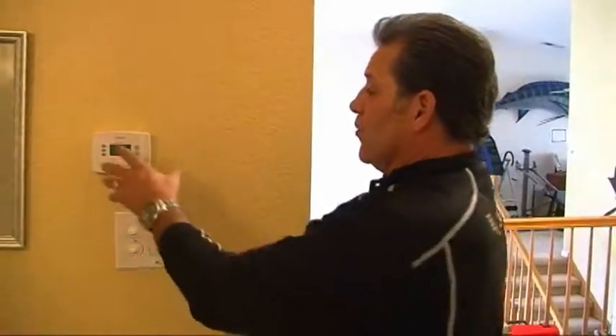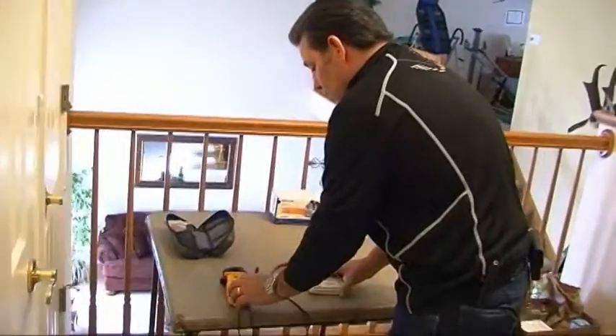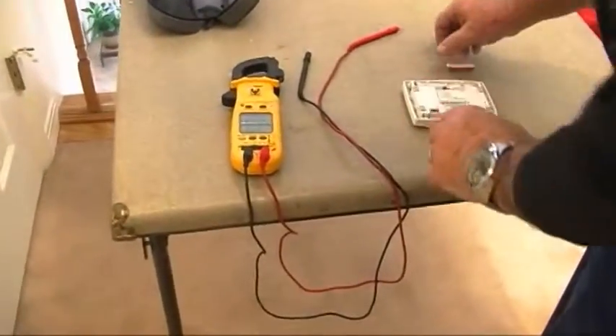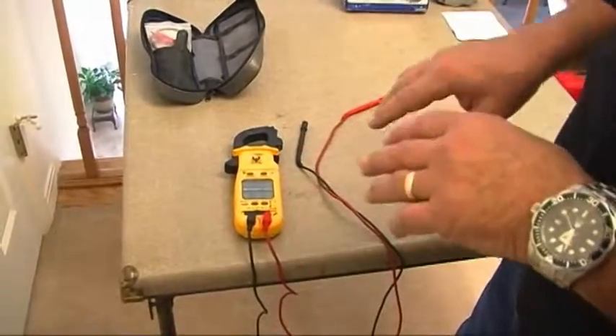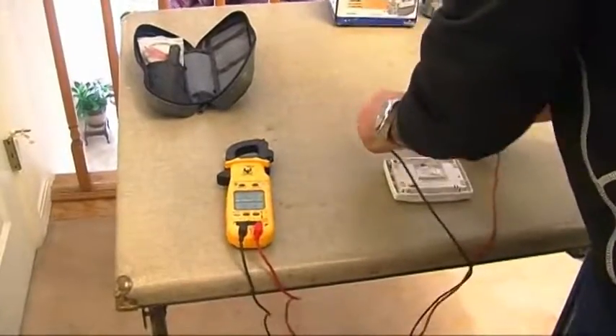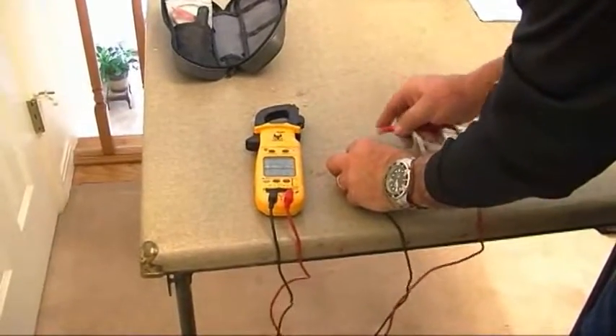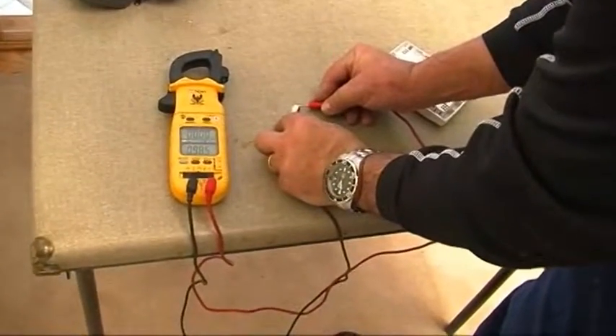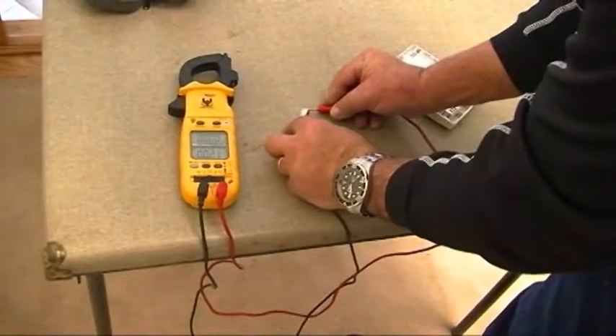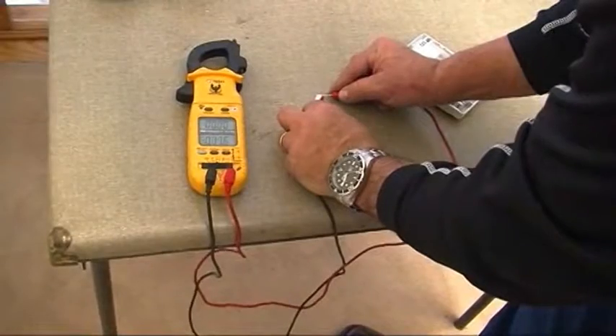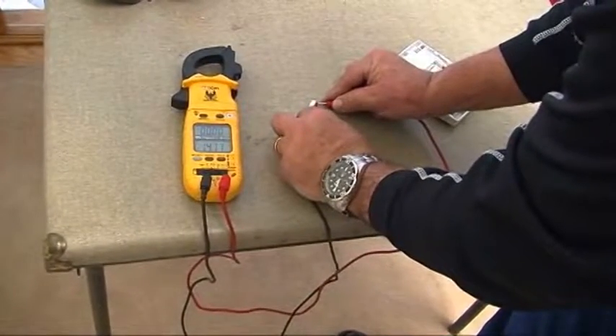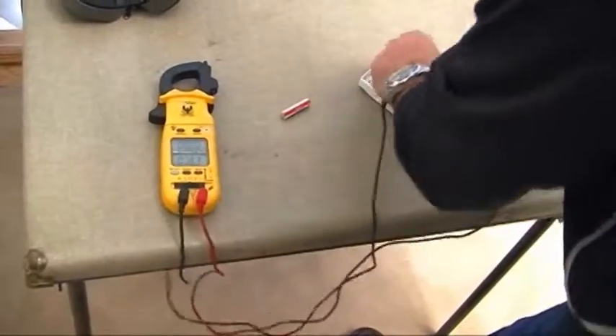Okay, the last step that I do when I'm doing a furnace overhaul or a furnace inspection is I come to the thermostat. This is a digital thermostat that has batteries. So I want to make sure that the batteries are good and they have a strong life left. If they don't, I want to replace them. So I come over here and I take my voltage meter, put it on millivolts. That's going to be the DC volts with the straight line with the 3 dashes underneath it, and it'll have a small M and a large V. So I'll take my batteries and I'll put my common on the flat side and my positive on the other side, and it shows me I have 1 point. It's jumping all over the place. Let's see here. I have 1.471 volts. So I'm almost at full life on that battery.